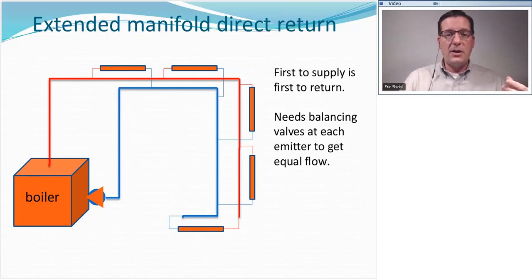So there's a circulator running continuously that's circulating water back and forth. We'll often have an automatic valve at each one of these emitters to allow the water to go through the emitter or not. And one of the problems with this system is that we have an unequal flow path. For example, the distance between the boiler through this emitter and back to the boiler is pretty short. That's where all the water is going to want to go. It's just going to want to go here. The water is not really going to want to push all the way down here and come back through.